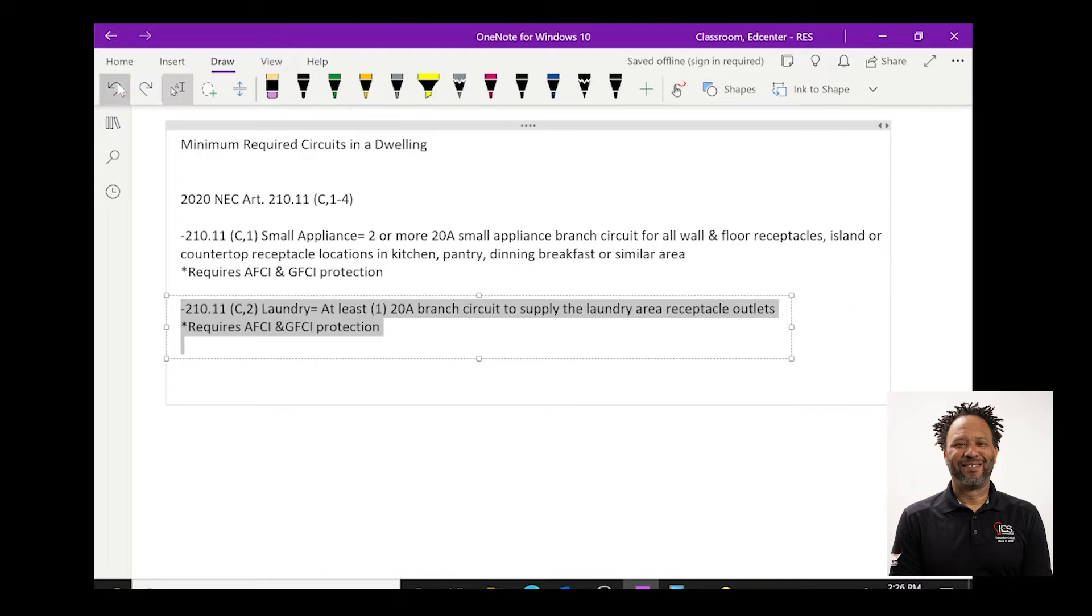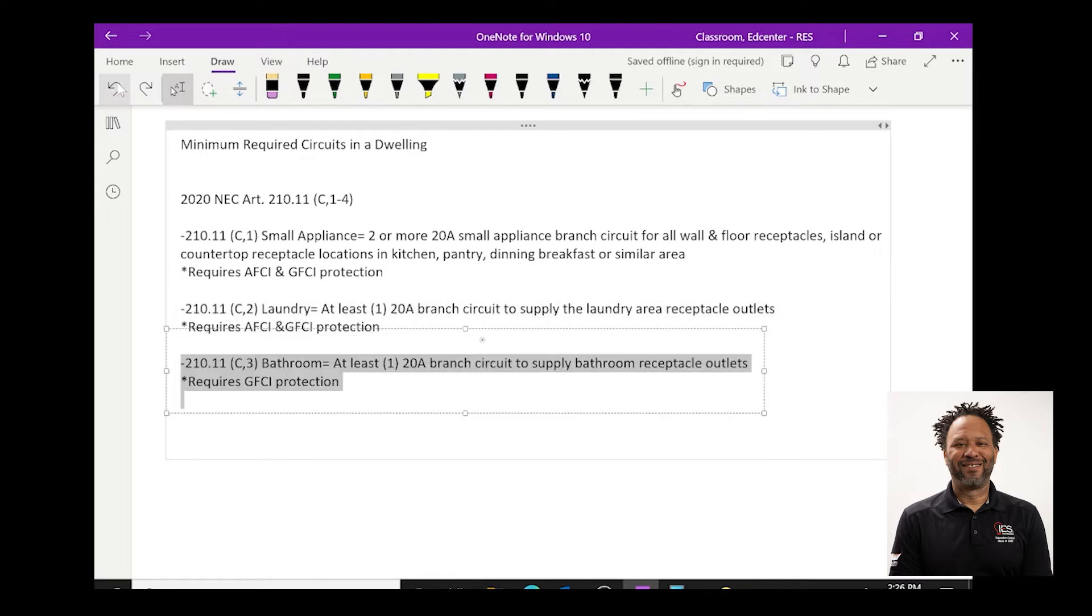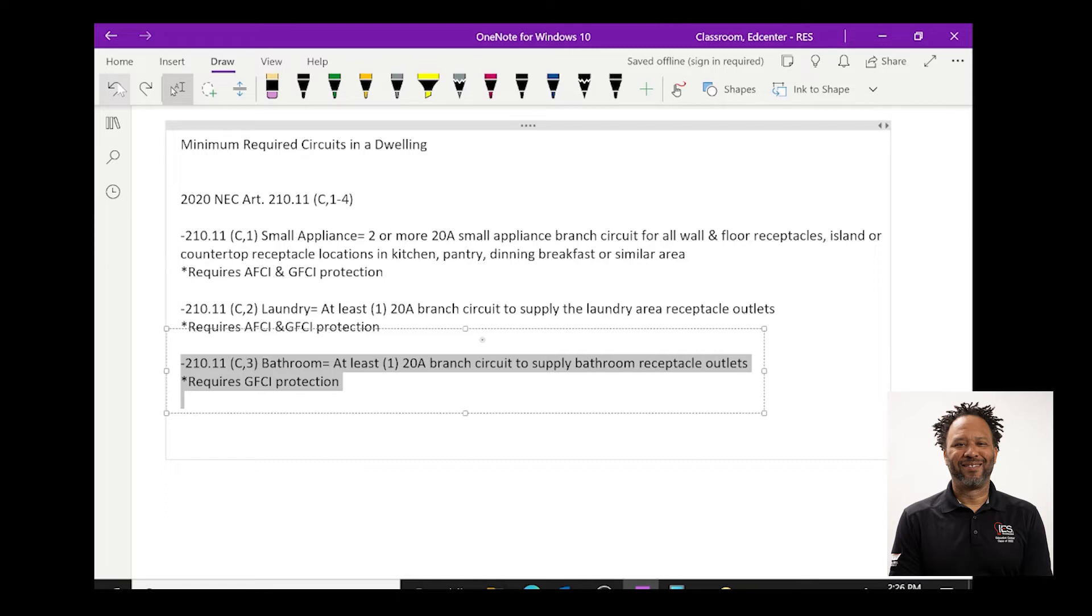The next circuit that is listed as required is your bathroom and that's article 210.11c3 and this states that at least one 20 amp branch circuit to supply all bathroom receptacle outlets is required. Now, this bathroom circuit only requires GFCI protection, no arc fault required for the bathroom outlet circuit.